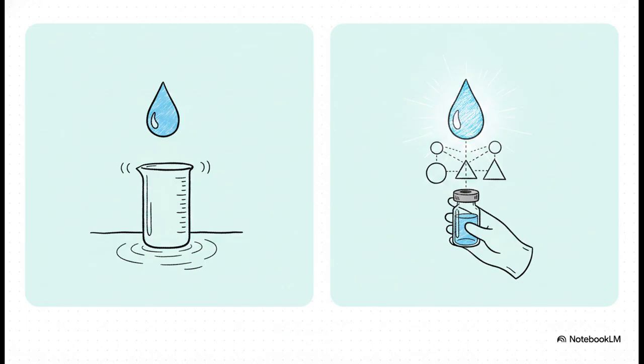So, purified water, or PW, is controlled for chemical and microbial quality, and it's perfectly suitable for your less critical applications. However, water for injection, commonly known as WFI, is the absolute highest grade of pharmaceutical water. There is no compromise here. It is mandatory for anything that directly touches the product during sterile manufacture. And yes, that includes the final rinses of your equipment.